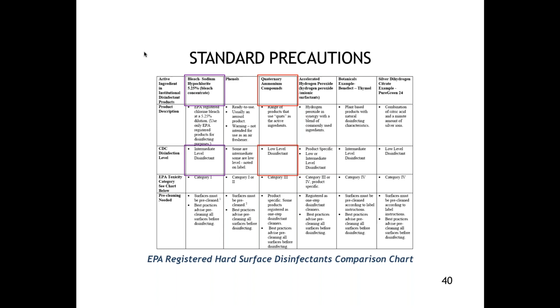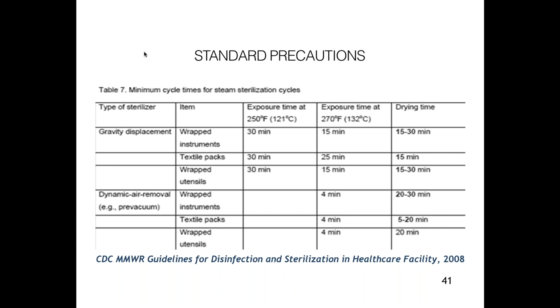So these are the things, and if you notice, at 250, most things are going to be 30 minutes. At 270, it really depends whether it's gravity displaced or pre-vacuum. And that's why you have to look and see what your device is. That's why most of our large hospitals prefer pre-vacuum systems that run at a minimum of 270, because then you can run your instruments over shorter periods of time.